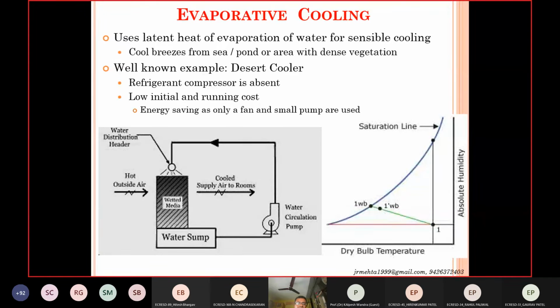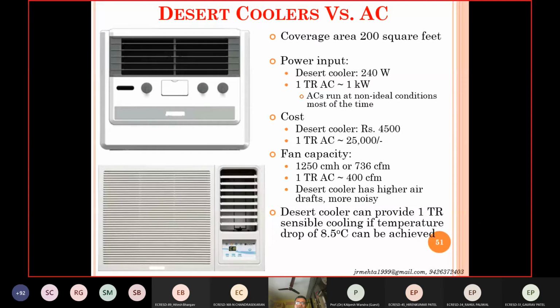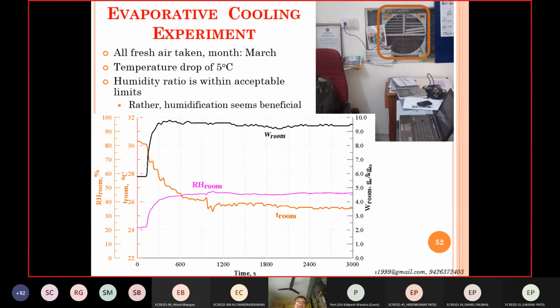So a desert cooler is not something which is unknown to us, which uses evaporative cooling. The advantage of that kind of cooler is the electrical power consumption for the same amount of sensible cooling. Actually, in evaporative cooling you are not reducing the enthalpy, you are just dropping the temperature. So if the incoming air is at required low humidity, then this technology is useful. For the same amount of sensible cooling, you will be consuming much lower electrical power. That's the advantage of evaporative cooling.